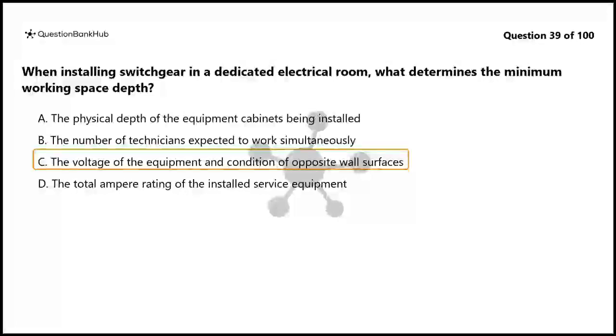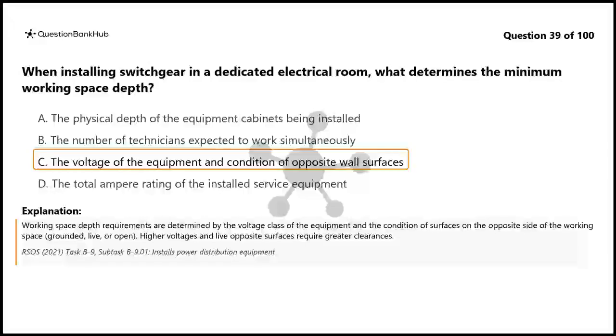The correct answer is C. The voltage of the equipment and condition of opposite wall surfaces. Working space depth requirements are determined by the voltage class of the equipment and the condition of surfaces on the opposite side of the working space: grounded, live, or open. Higher voltages and live opposite surfaces require greater clearances.